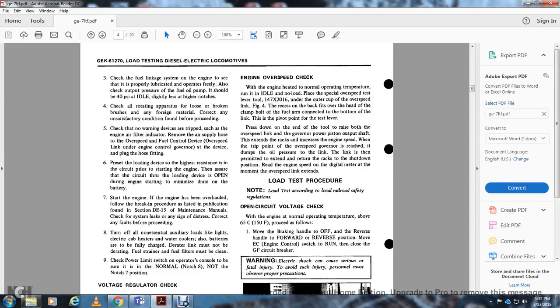Both move with the overspeed link and the governor power piston output shaft, extending the rack to increase the engine speed until the trip point of the overspeed governor is reached, which dumps the oil pressure into the link. The link is then permitted to extend, returning the racks to the shutdown position. Read the engine speed with the digital meter at the moment the overspeed link extends.